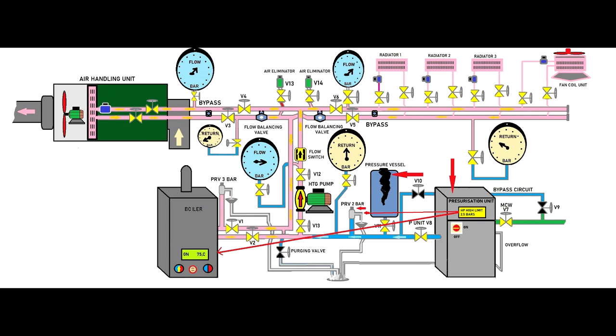Because you don't want to lose heating agent from the system. Some people are using only water, but some people who use, as an example, chillers or combined systems are using glycol which is very expensive, plus sometimes you use some substances to balance the heating agent like inhibitors. So we don't want to lose that one. That's why the pressurization unit will stop the system first. Unfortunately, some technicians are diabolic - they have a lot of knowledge and their knowledge is equal with their laziness. Instead of checking the pressure vessels or the system, they're just happy to change the settings of the pressurization unit.